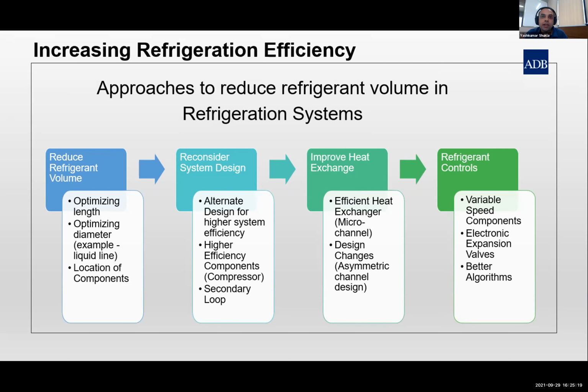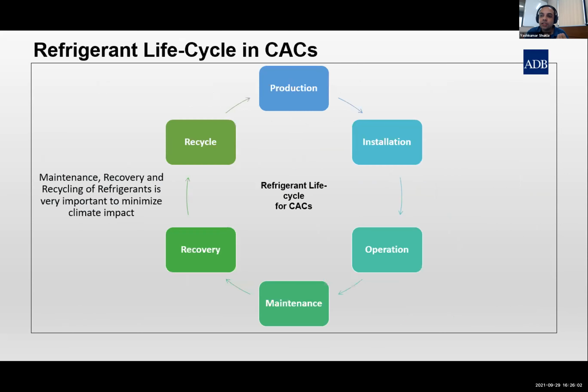The third approach is improving the heat exchange within the refrigeration system. You can think about more advanced, efficient heat exchangers, such as microchannel heat exchangers, or changes in design: instead of a symmetric design, you may think about an asymmetric channel design, where you can try to minimize refrigerant volume and increase the efficiency of heat exchange within the refrigeration system. And finally, the controls. You can think about better algorithms. You can use electronic expansion valves instead of thermostatic expansion valves, and variable speed components. So these are the ways we can reduce the refrigerant volume in refrigeration systems and increase refrigeration efficiency.